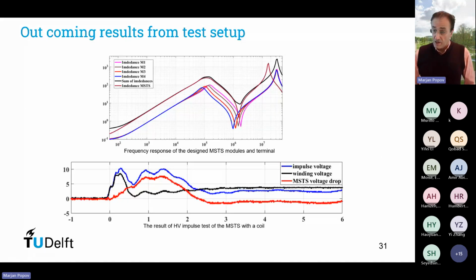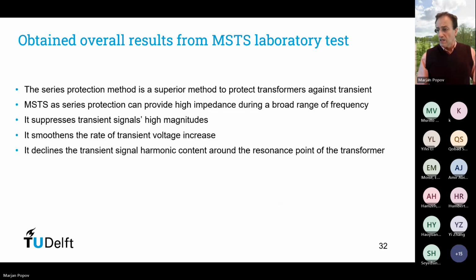Of course, this is a device to suppress resonance frequencies. However, normally we still have to keep the surge arrester as a device to limit the amplitude of the overvoltages. There are quite some advantages of this device, and all this has been reported in the paper, with a lot of measurements, and you can find a lot of data there.